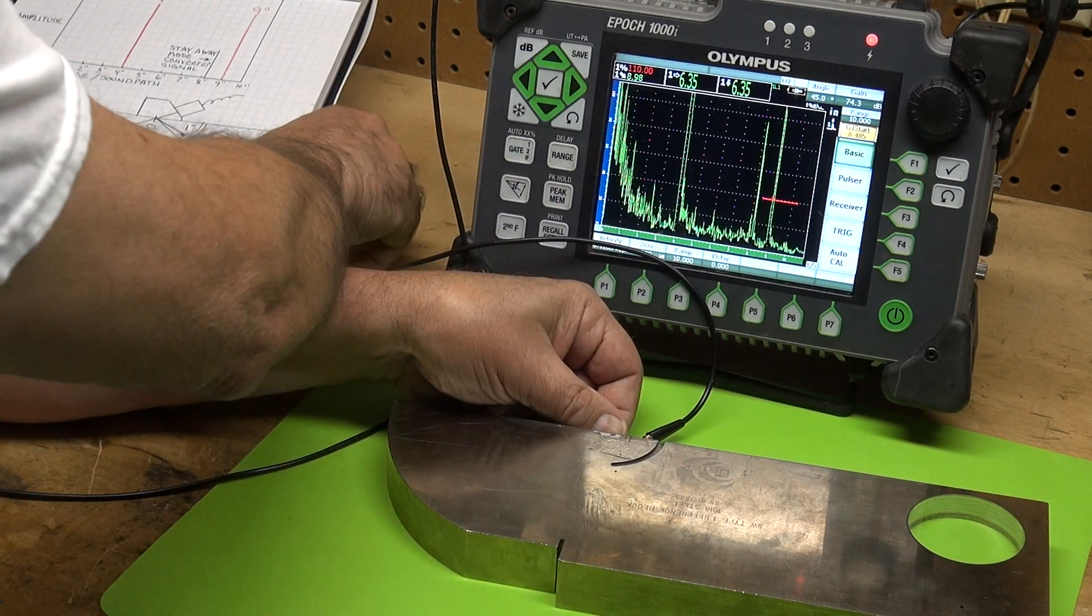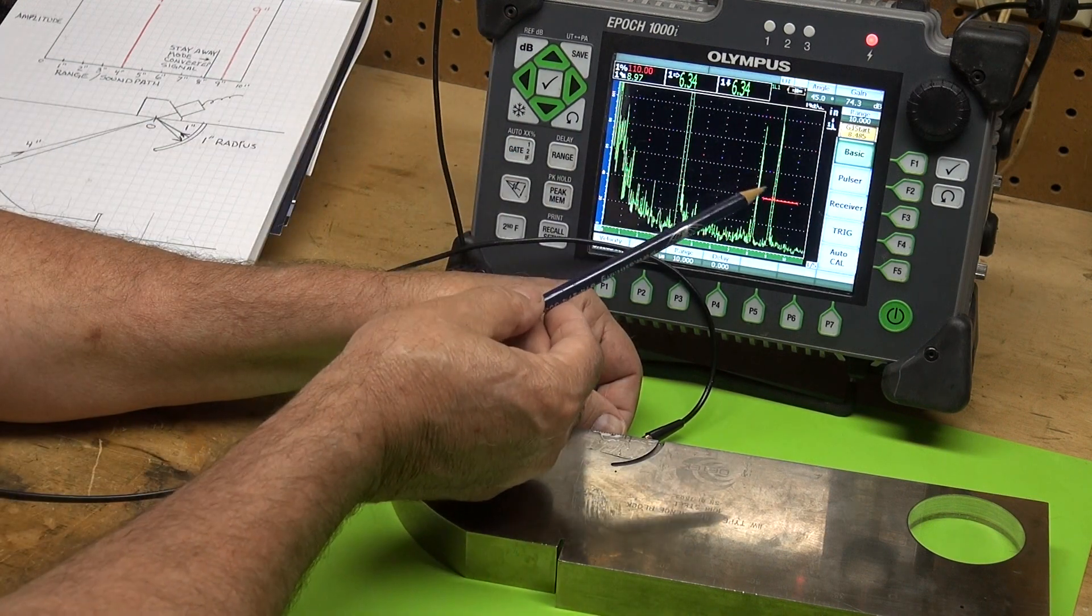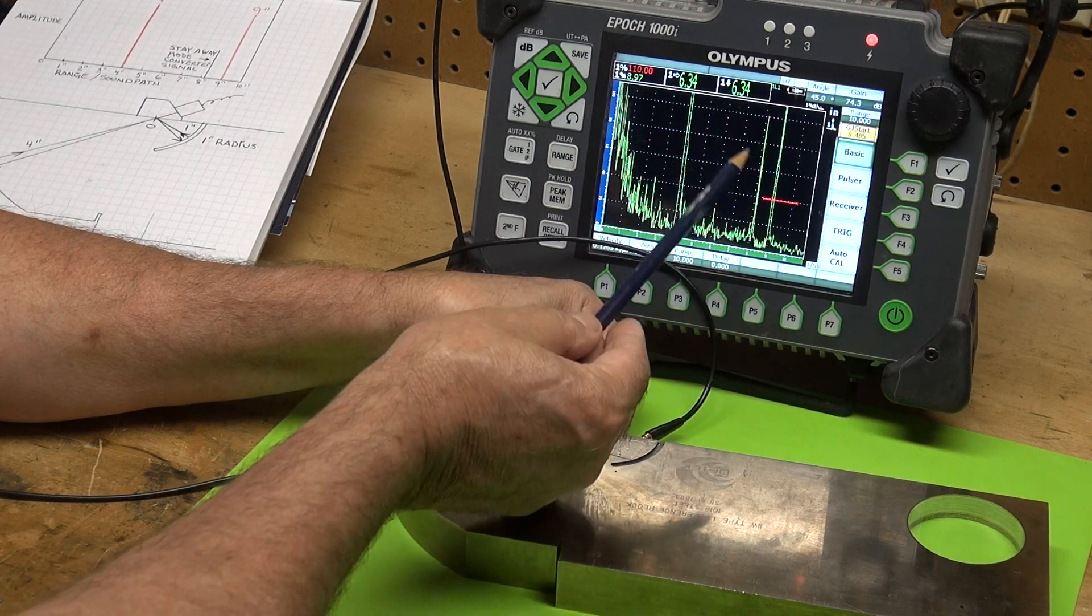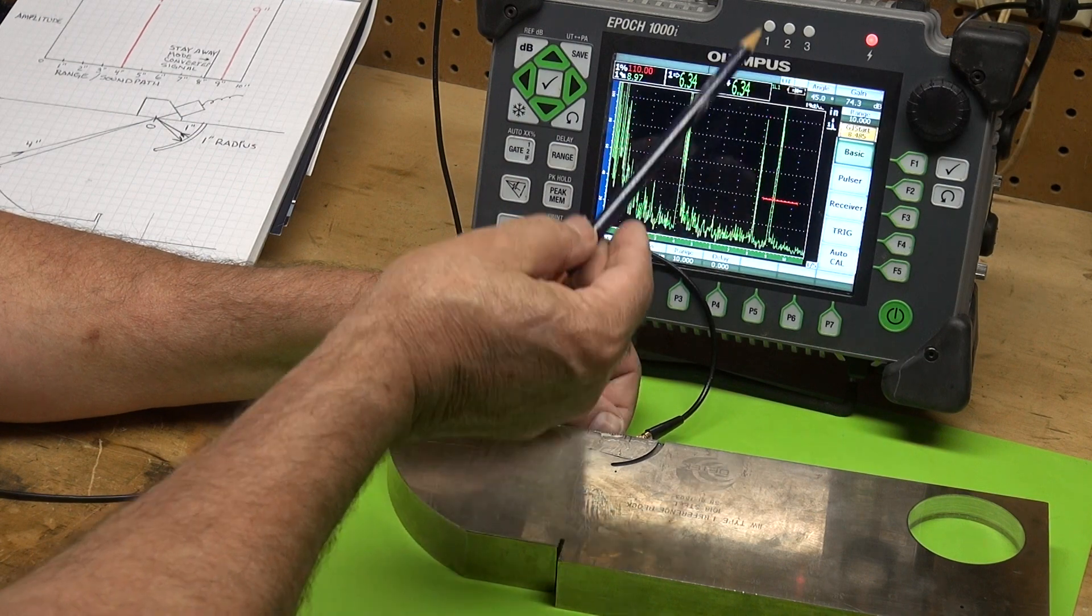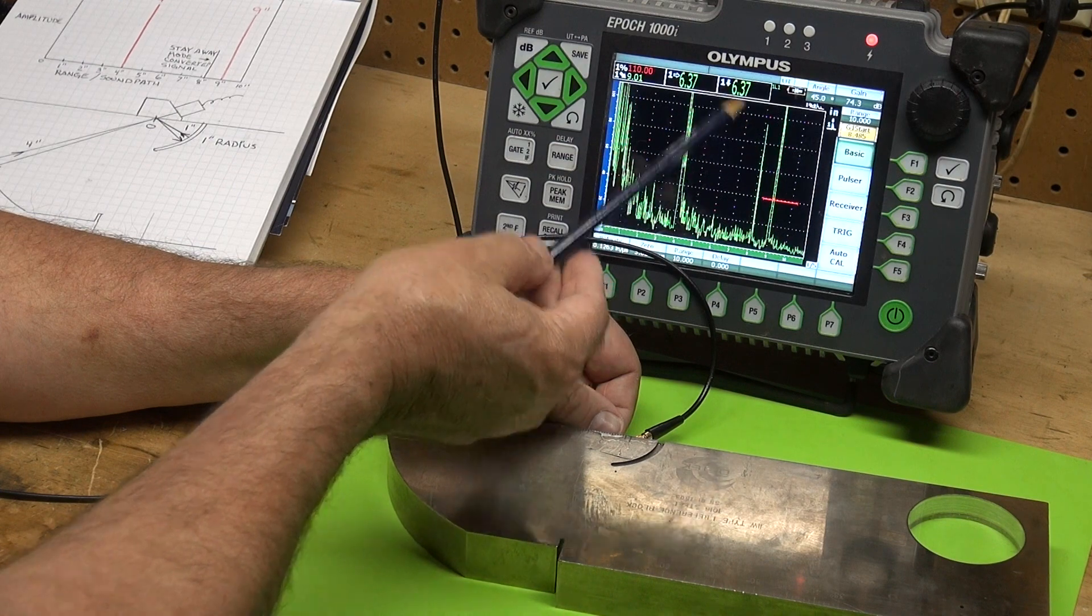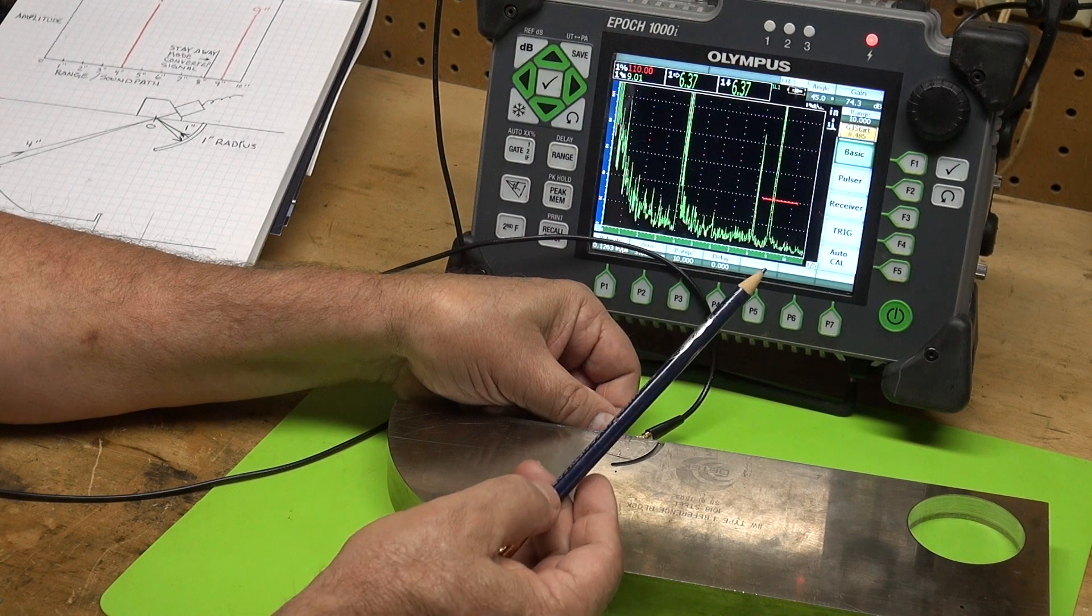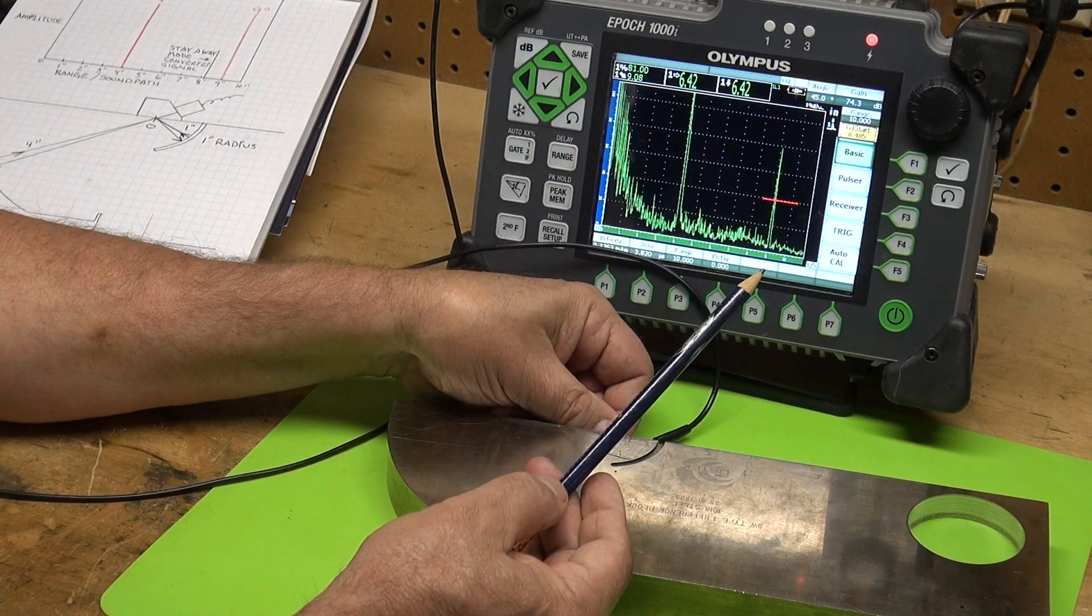That signal jumping up is trying to entice you and it's a mode converted signal, not the radius. So if you put your gate over this and calibrate with that reflector, you're going to be wrong. Your velocity is going to be wrong and your zero.